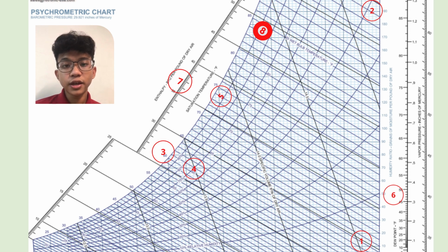And look at step 4, locate the interior curve lines. Each of the curve lines represents a certain level of relative humidity in percent. And look at step 5, on the right side of the chart, you must locate the vertical line labeled dew point. The dew point is expressed as a temperature. The dew point lines traverse the chart as a horizontal line.